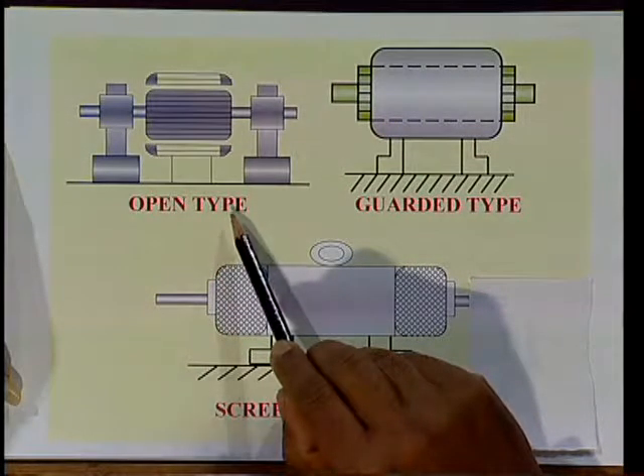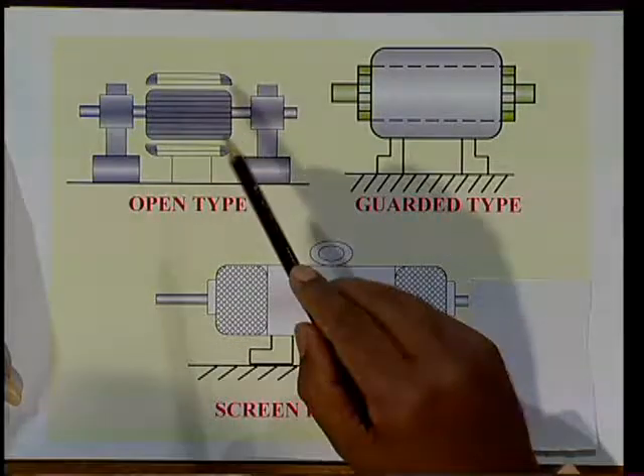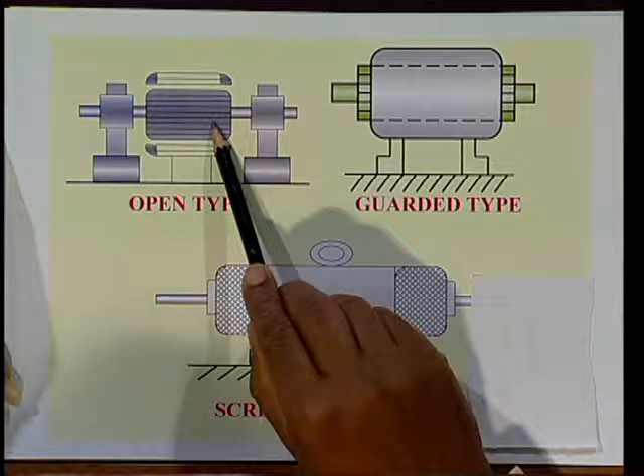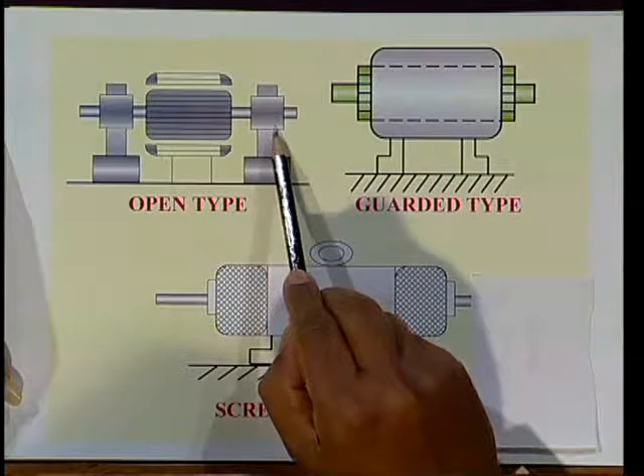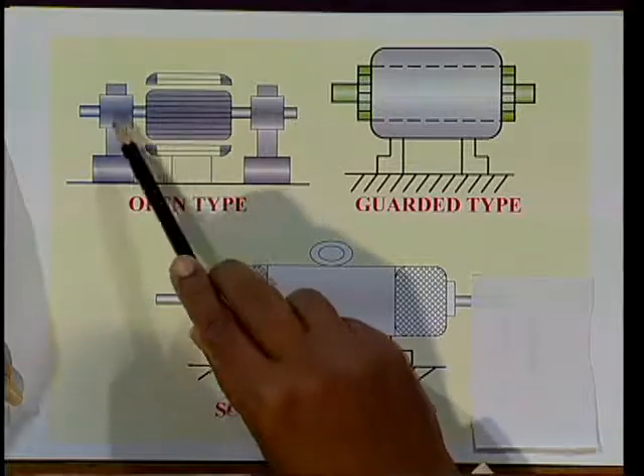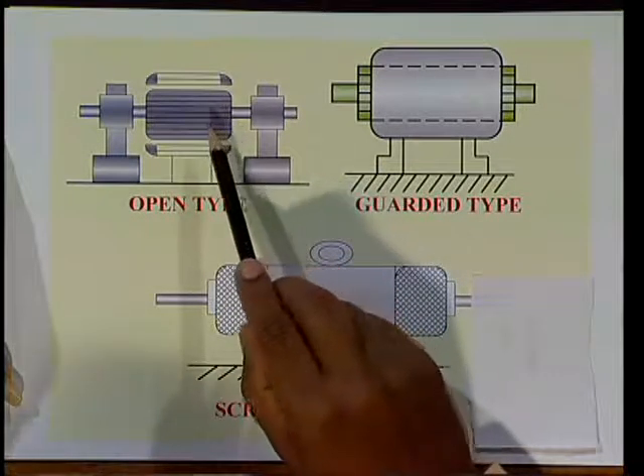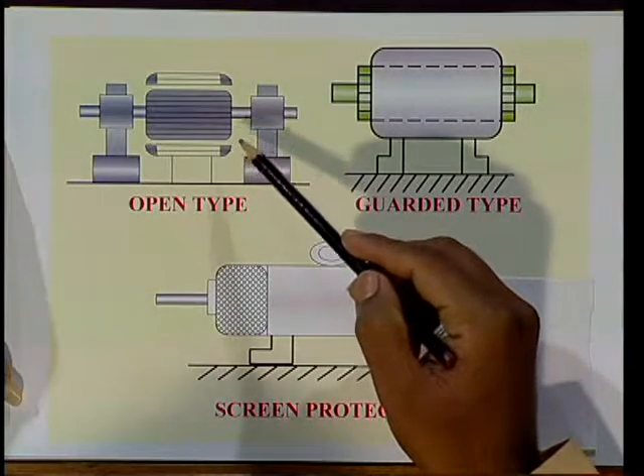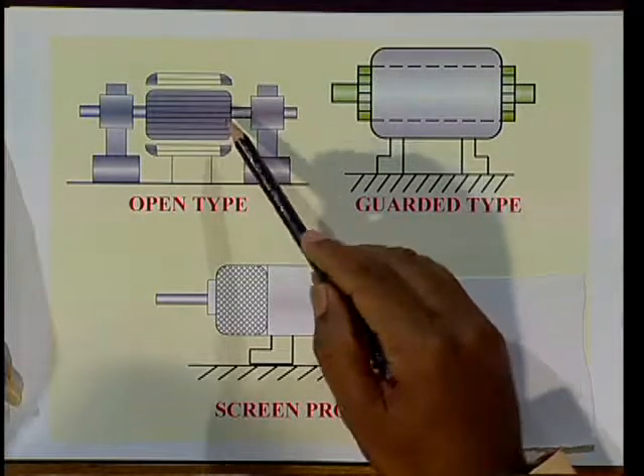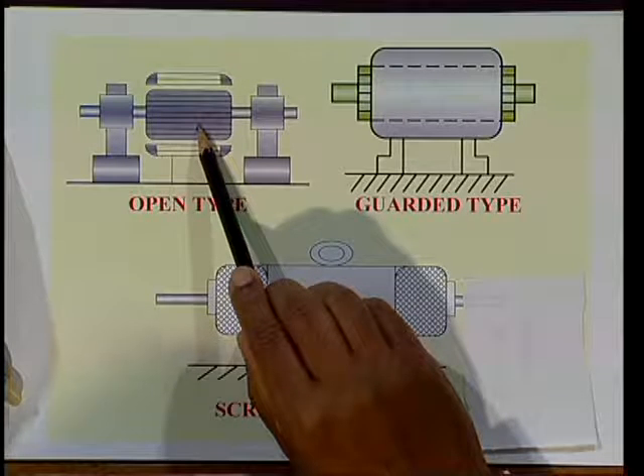In open type enclosures, the stator and rotor are exposed to free contact with air, with the rotor supported on bearings. Due to exposure to surrounding air, there may be chances of deposition of dust, dirt, and other moisture particles. Hence, we have to place this motor in a separate, neat, and clean room. Generally, this type of motor is used for large-size DC generators and motors.